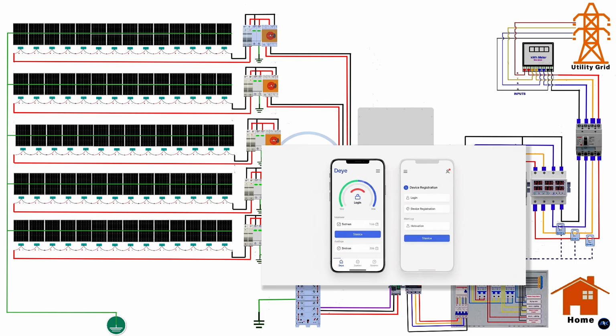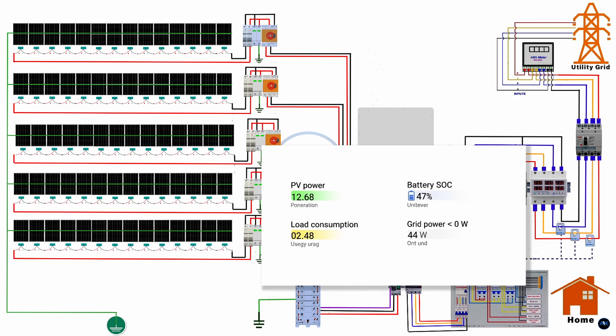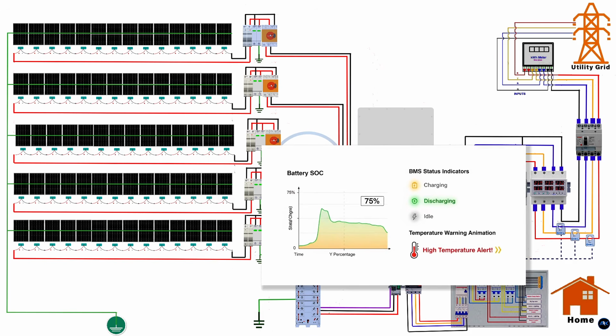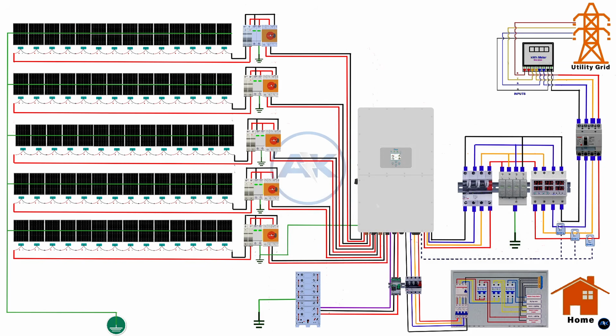Daily monitoring helps detect issues early. Key values to check include solar production, inverter output, grid power, and battery state of charge. In zero export systems, always verify that grid export remains at or near zero. For the high-voltage battery system, monitor state of charge, charge and discharge power, and alarms. The battery management system automatically protects against overvoltage, overcurrent, and temperature extremes. Any repeated alarms should be investigated immediately.